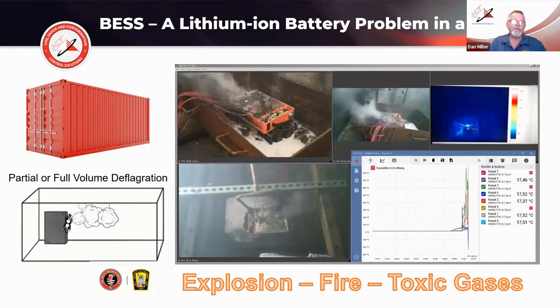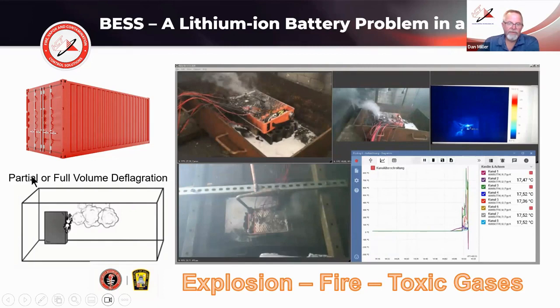Everybody has to be aware of battery energy storage systems. As batteries sit at a lower state of charge, they tend to emit more explosive, flammable, and toxic gases and fill that container up. Any ignition source, either internal or external, can set it off into an explosion. So an F500 system built into a battery energy storage system is an excellent solution to prevent that in a non-human intervention way.